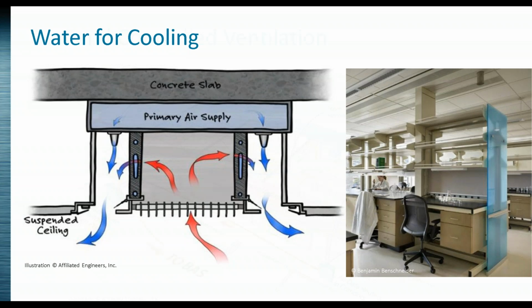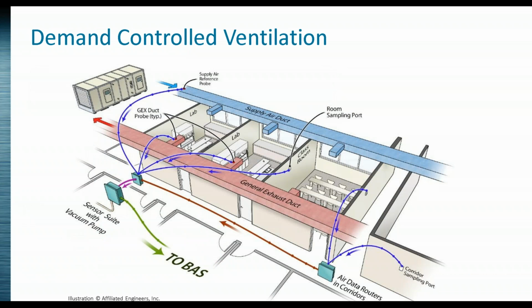We see demand control ventilation, really looking at real-time feedback—what should that minimum air change rate be? Should it just be set by time clock or occupancy, or based on actually figuring out what's going on in the spaces? Should we have something more dynamic? ASHRAE and other organizations, including in Canada with vivariums, are looking at alternatives to turn down based on sensing. So there's a lot going on.